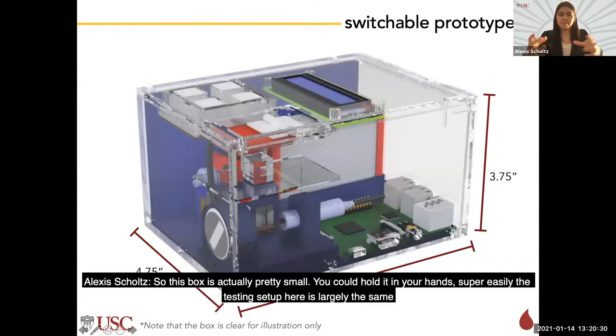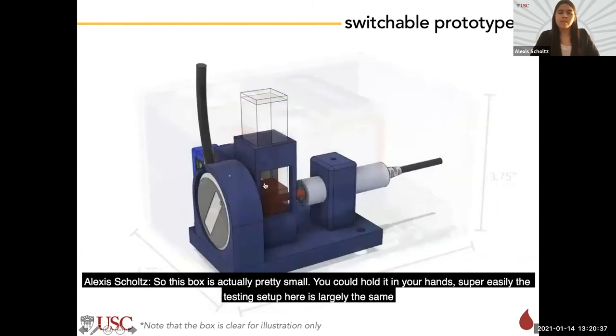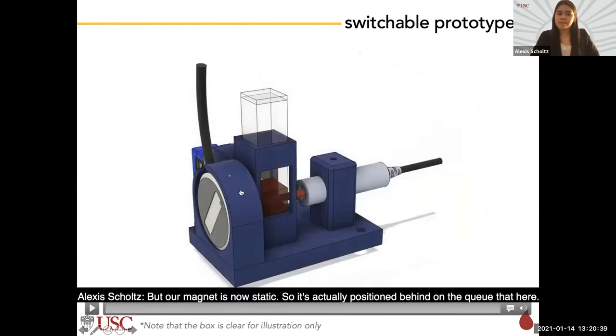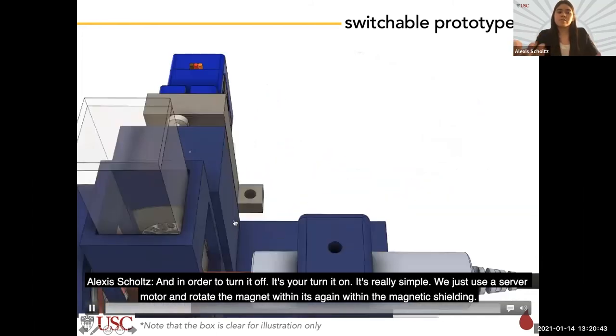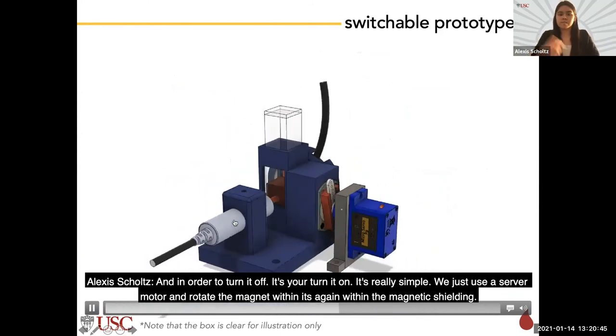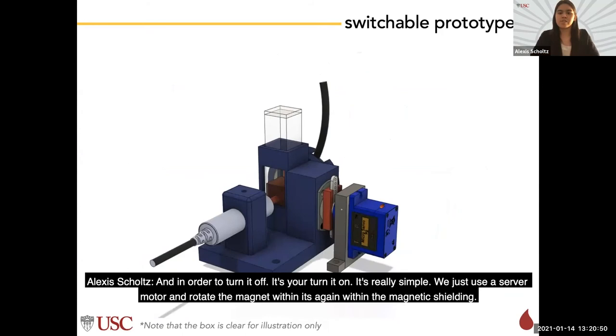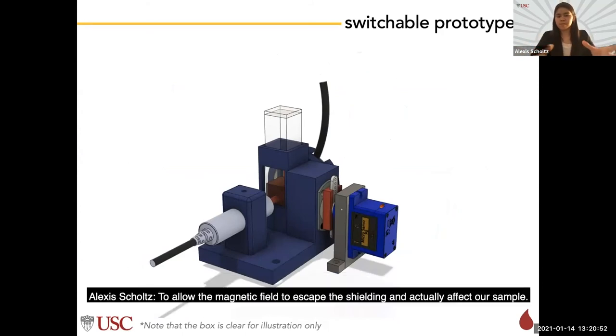This box is actually pretty small—you could hold it in your hands easily. The testing setup here is largely the same, but our magnet is now static, positioned behind the cuvette. To turn it off is really simple: we just use a servo motor to rotate the magnet within the magnetic shielding, allowing the magnetic field to escape the shielding and actually affect our sample.